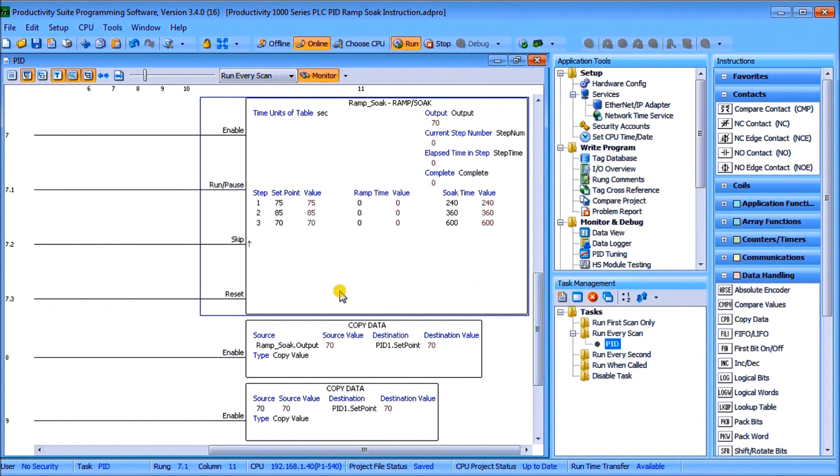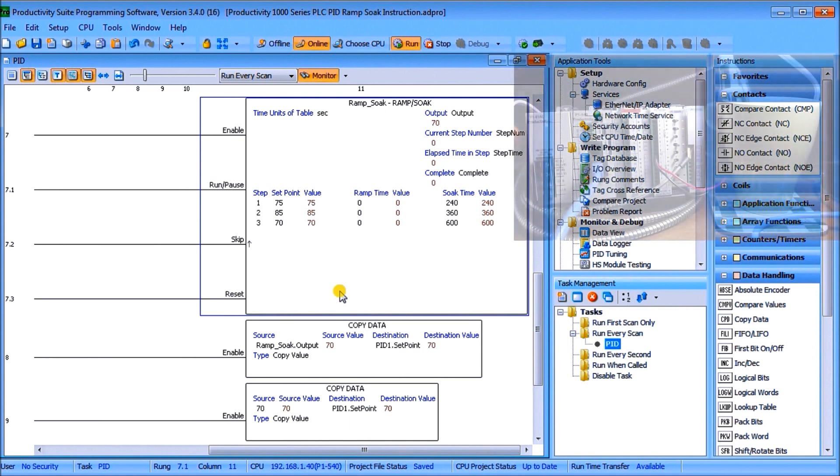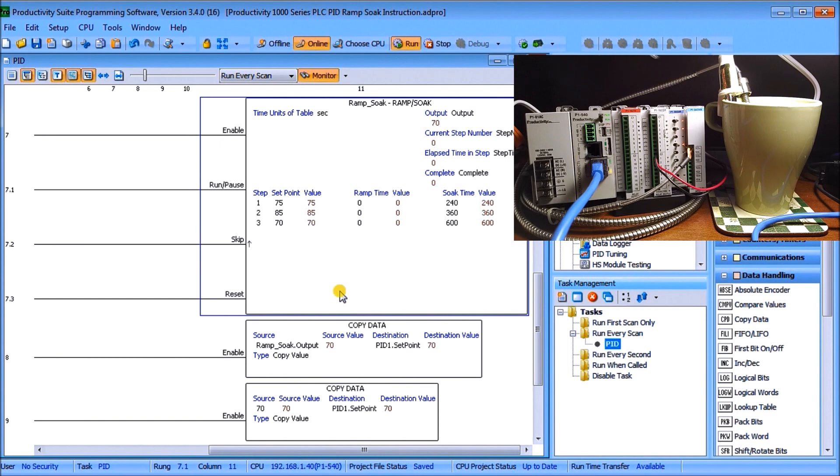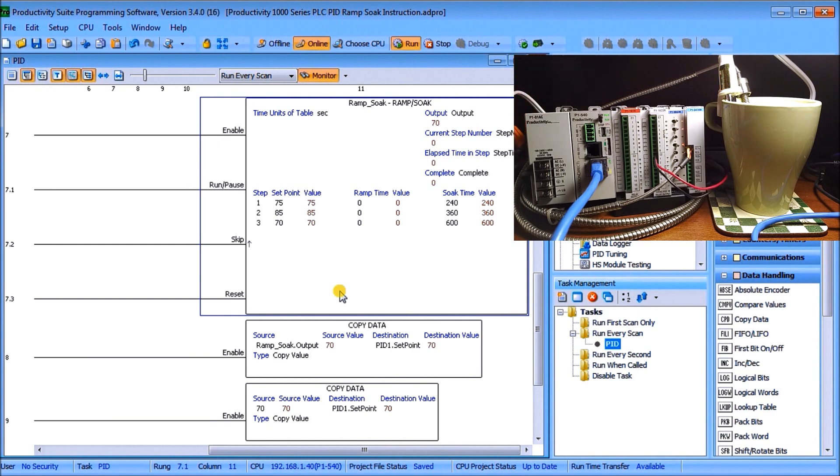So here I'm communicating to my ethernet port right here and then I have my thermocouple input card which has been wired into my thermocouple which is in my cup of water, and then I have my output which is then going into my immersion heater located right here. And that immersion heater, our output is spliced into the power cord to actually turn it on and off and this is our actual relay that we can see cycling to maintain that temperature that we've set.